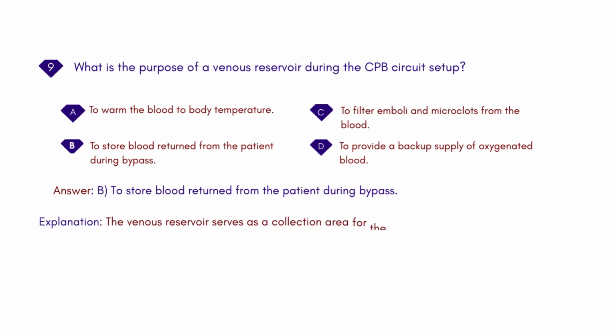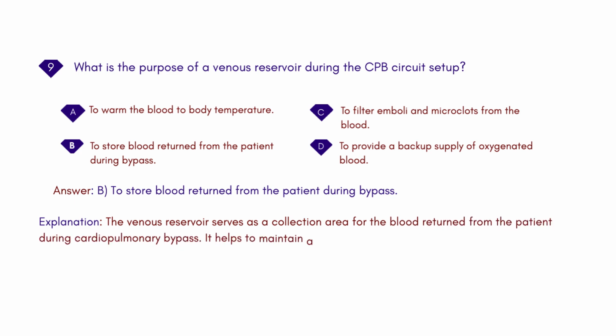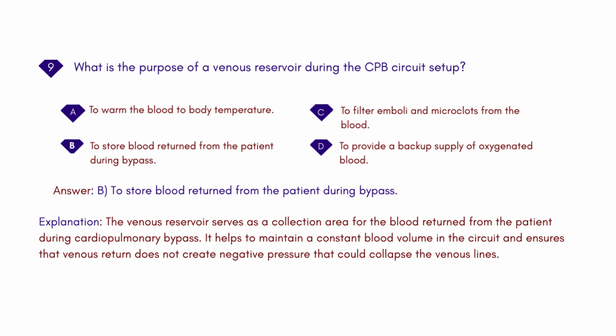Explanation: the venous reservoir serves as a collection area for the blood returned from the patient during cardiopulmonary bypass. It helps to maintain a constant blood volume in the circuit and ensures that venous return does not create negative pressure that could collapse the venous lines.